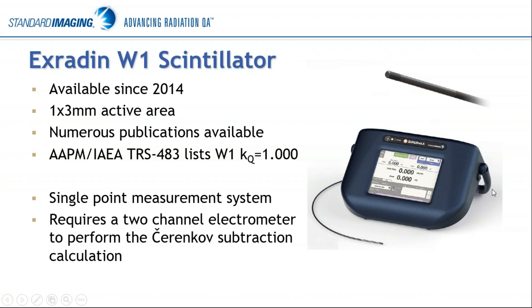It does require a two-channel electrometer like our SuperMAX electrometer to perform that Cherenkov subtraction. You can use it with two single-channel electrometers, but the timing is a little more tricky and you would have to do all of the corrections by hand.